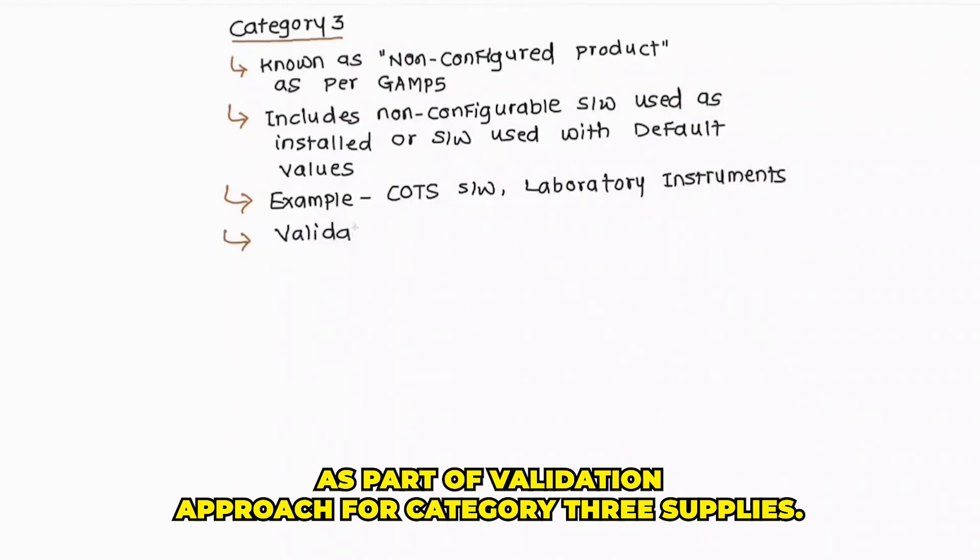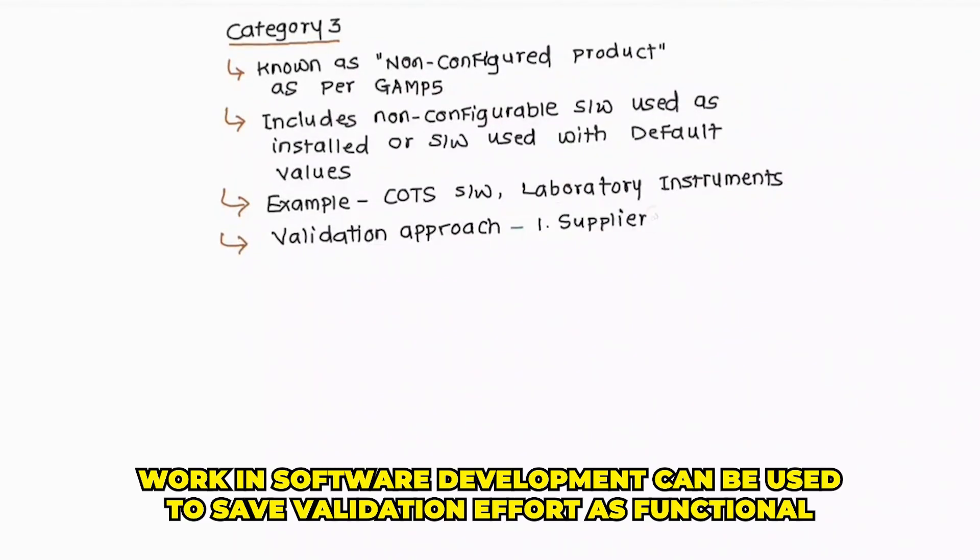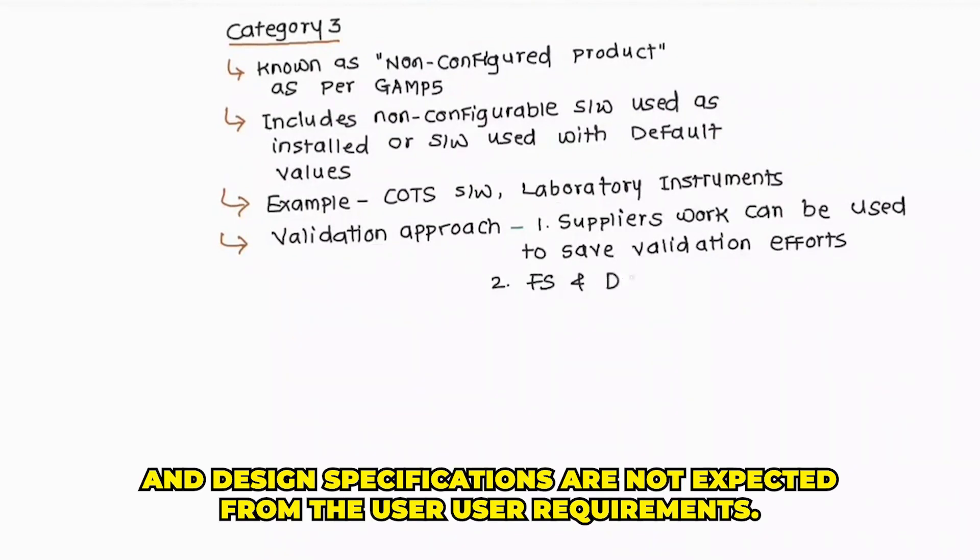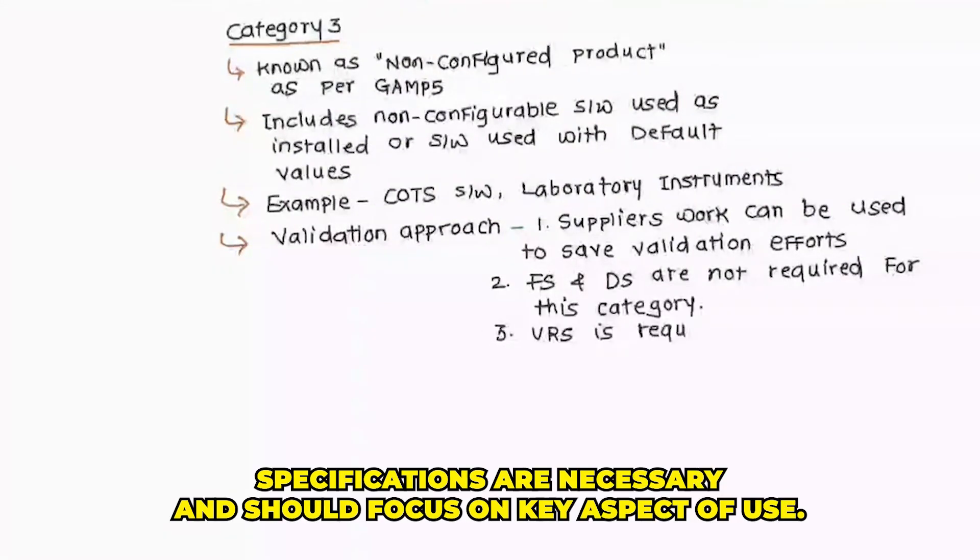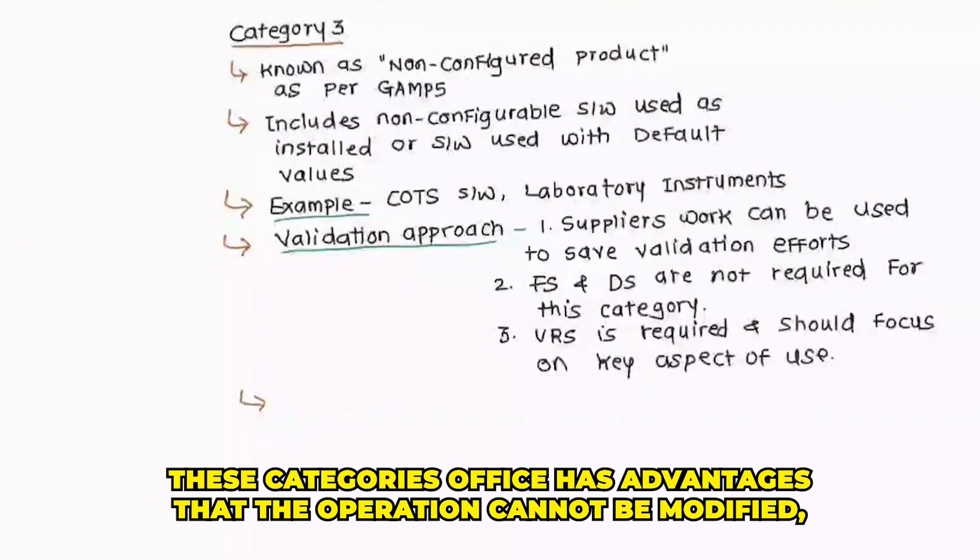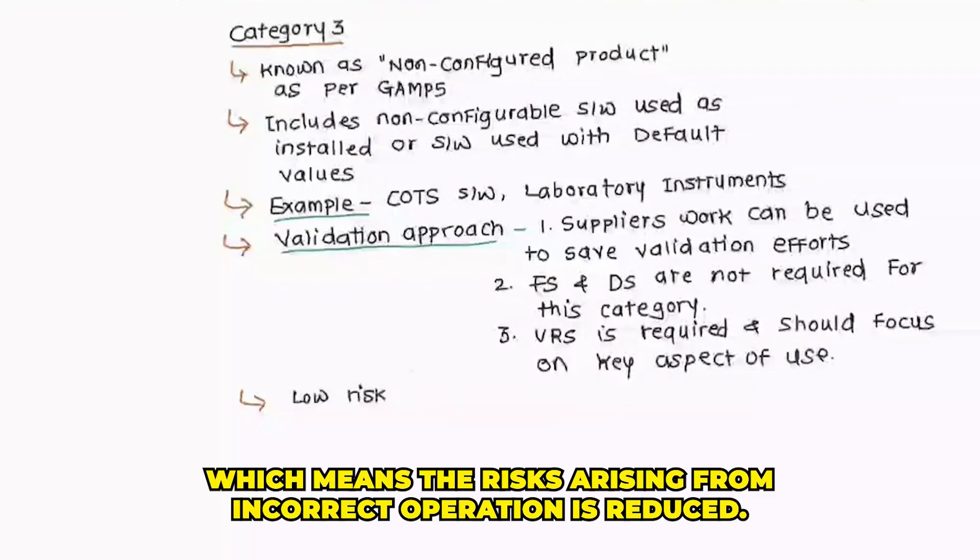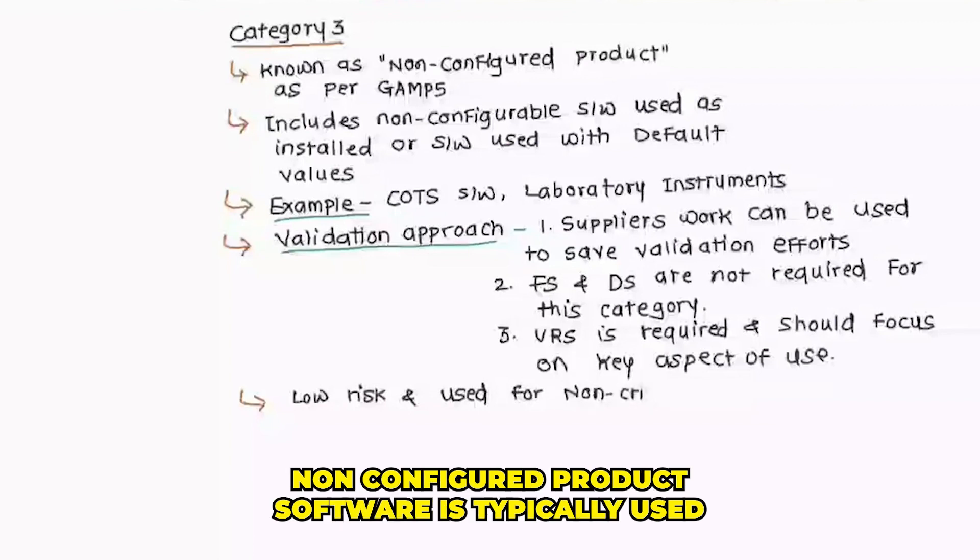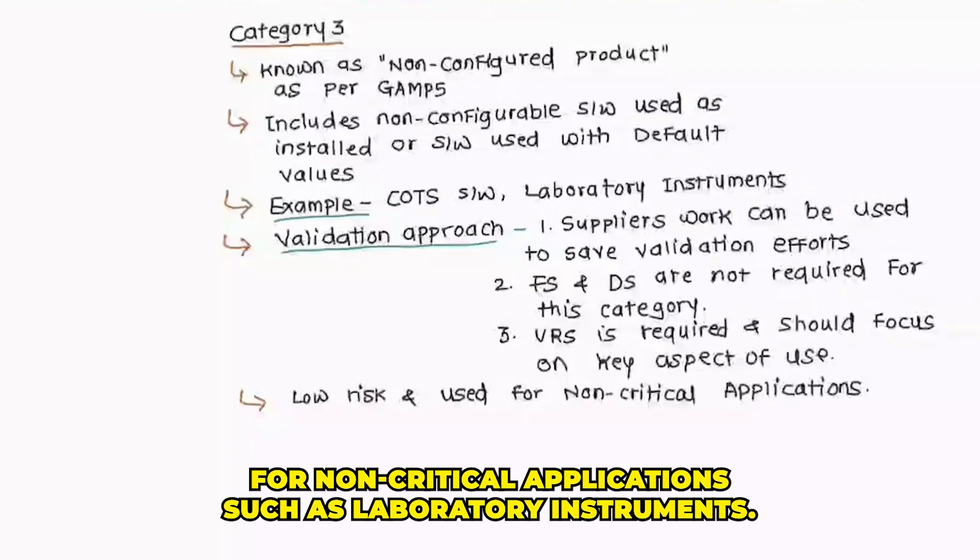As part of validation approach for category 3, suppliers work in software development can be used to save validation effort, as functional and design specifications are not expected from the user. User requirement specifications are necessary and should focus on key aspects of use. This category software has an advantage that the operation cannot be modified, which means the risk arising from incorrect operation is reduced. Non-configured product software is typically used for non-critical applications such as laboratory instruments.